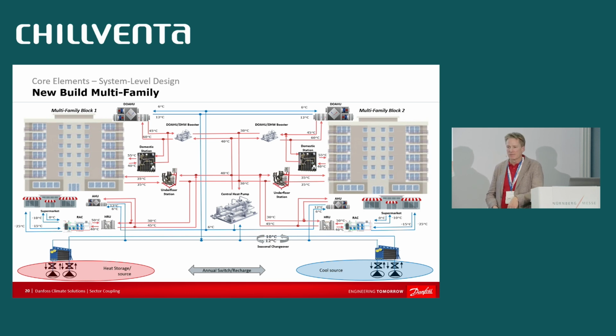This is a good example, a literal project we're working on right now, applying heating from an aquathermal energy storage system that's boosted to the underfloor heating temperature. You only boost further what's required for the domestic hot water and for the dedicated outdoor air ventilation going into that same building.